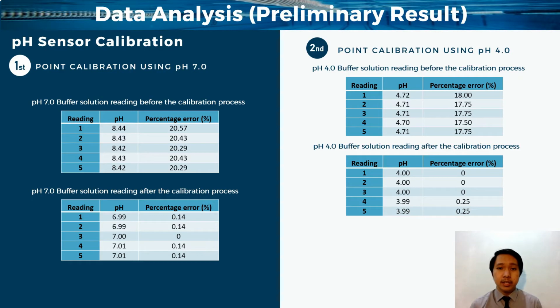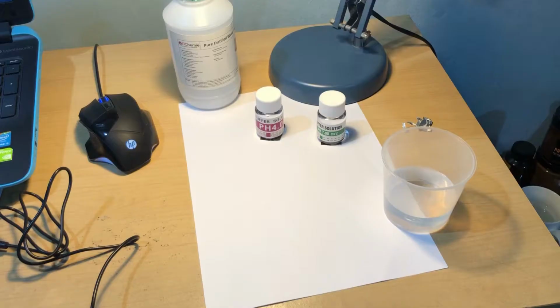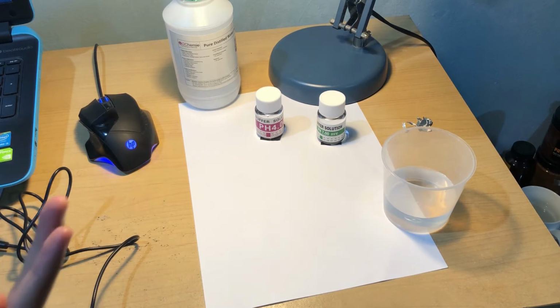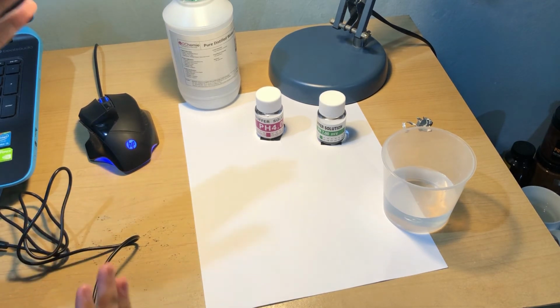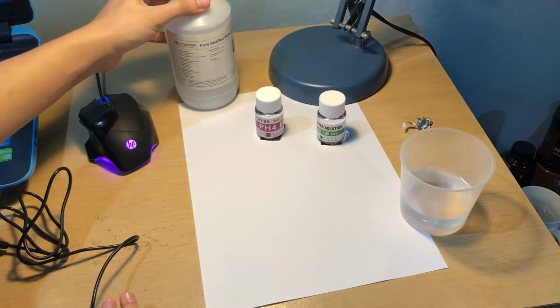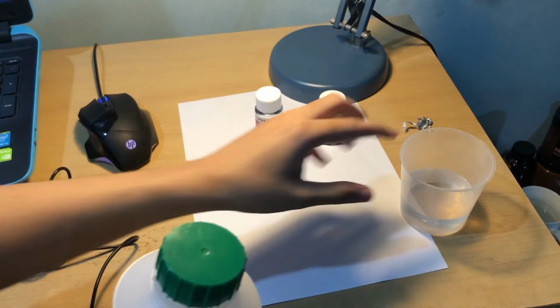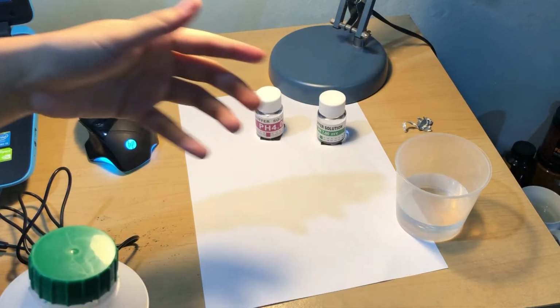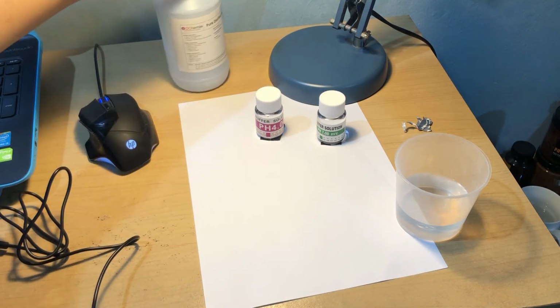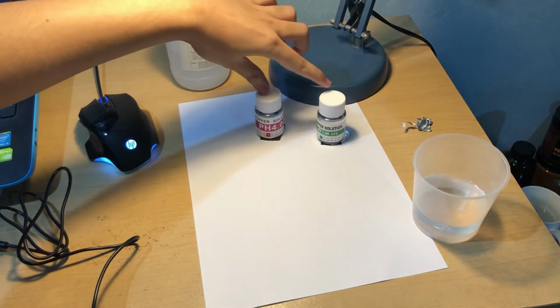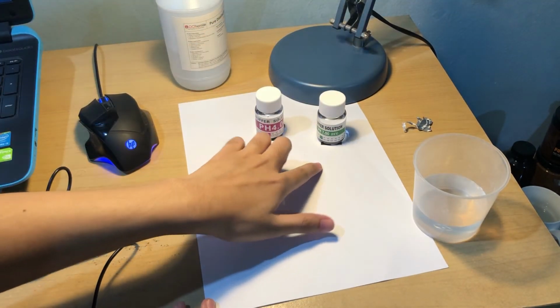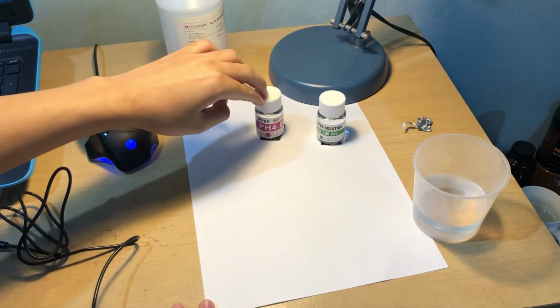Before the data analysis of the calibration process, I will demonstrate the calibration process. Okay, so now I'm going to calibrate the pH sensor that is going to be used on my system. So we need 3 solutions here. The first one is pure distilled water, the one that I already poured here. It's going to be used to clean the probe during the calibration process. And the other 2 solutions are the buffer solution with pH of 7 and also pH 4.